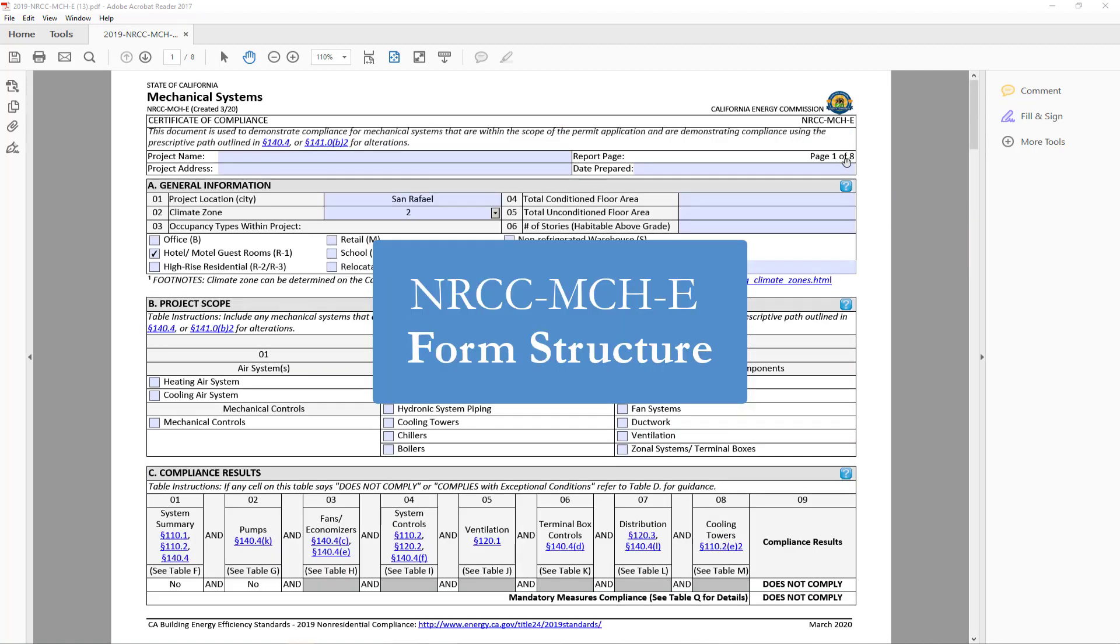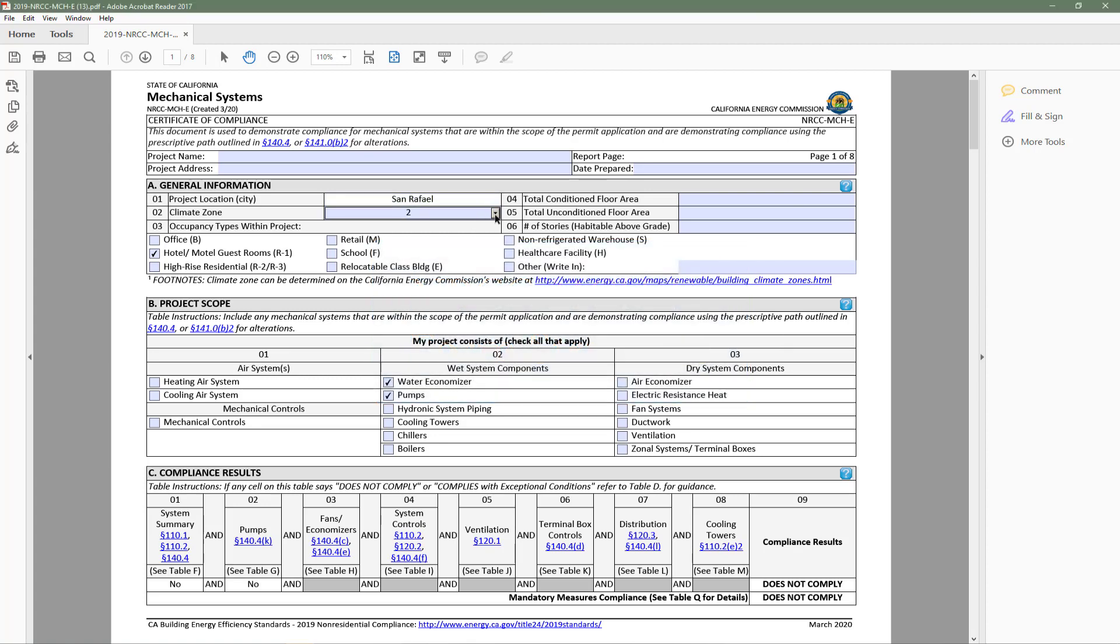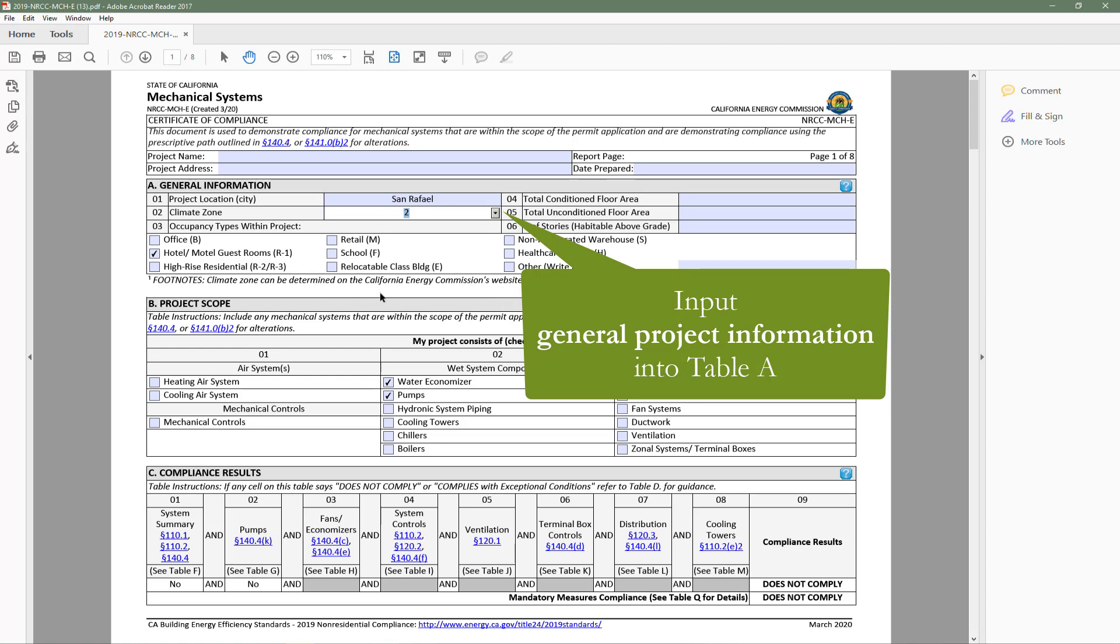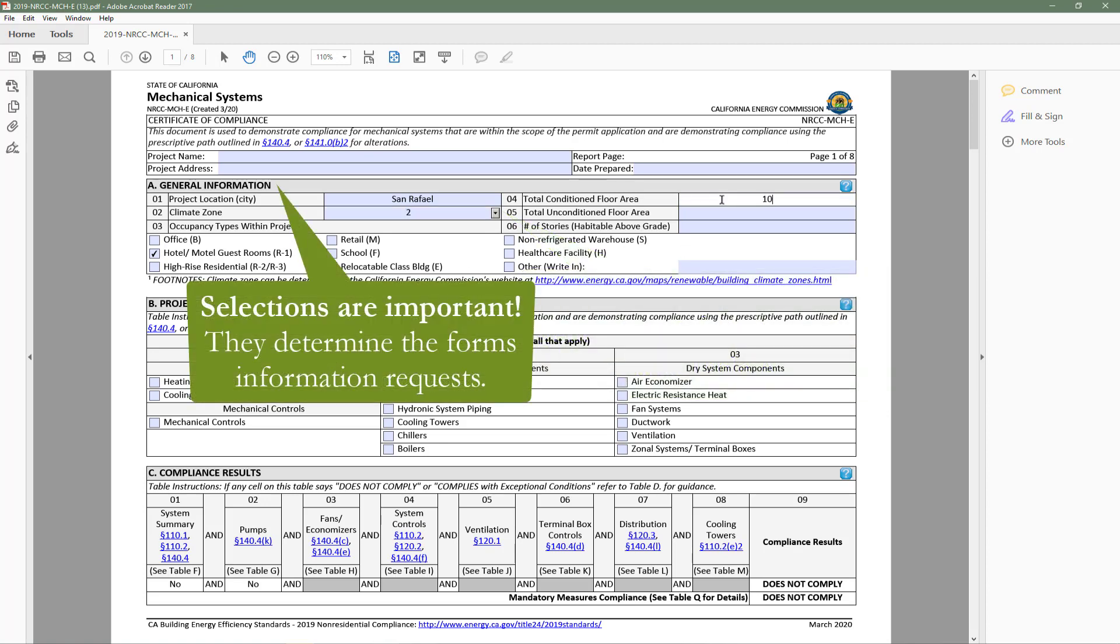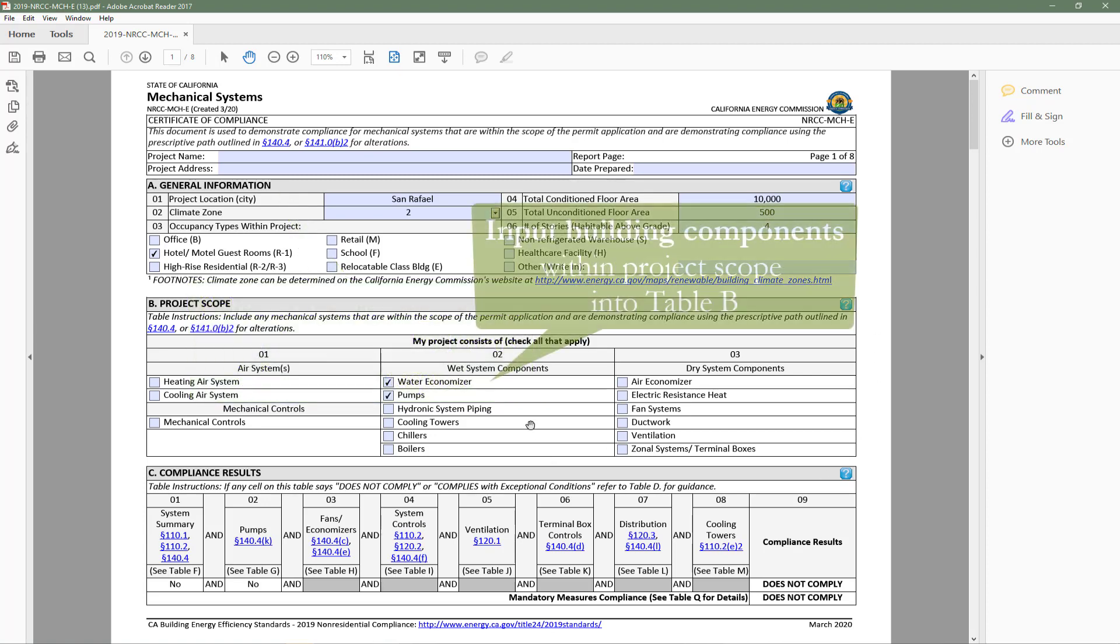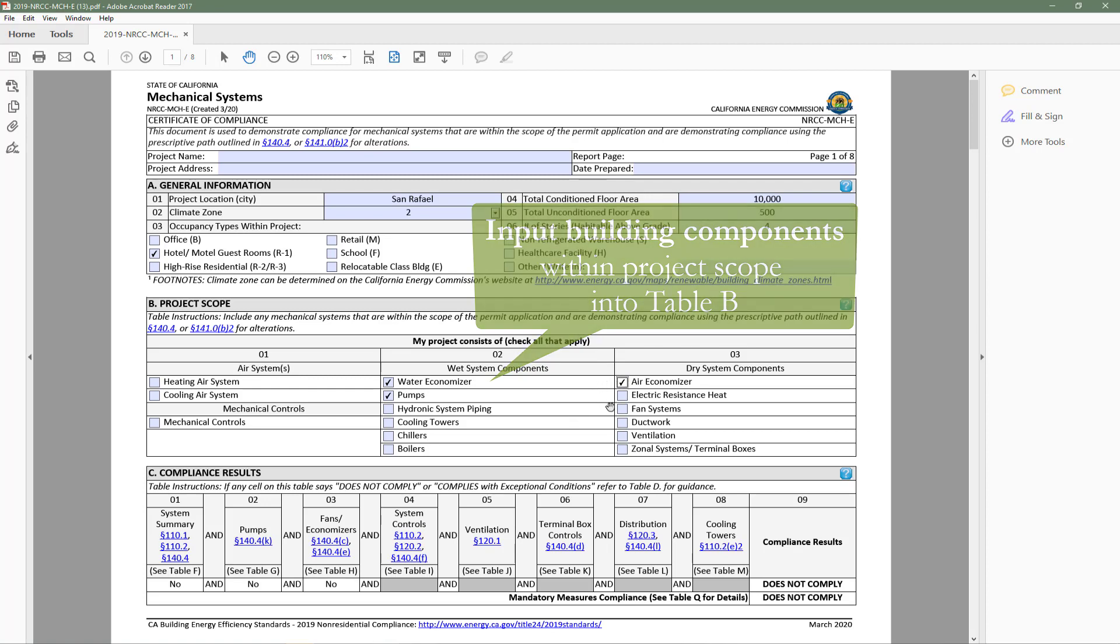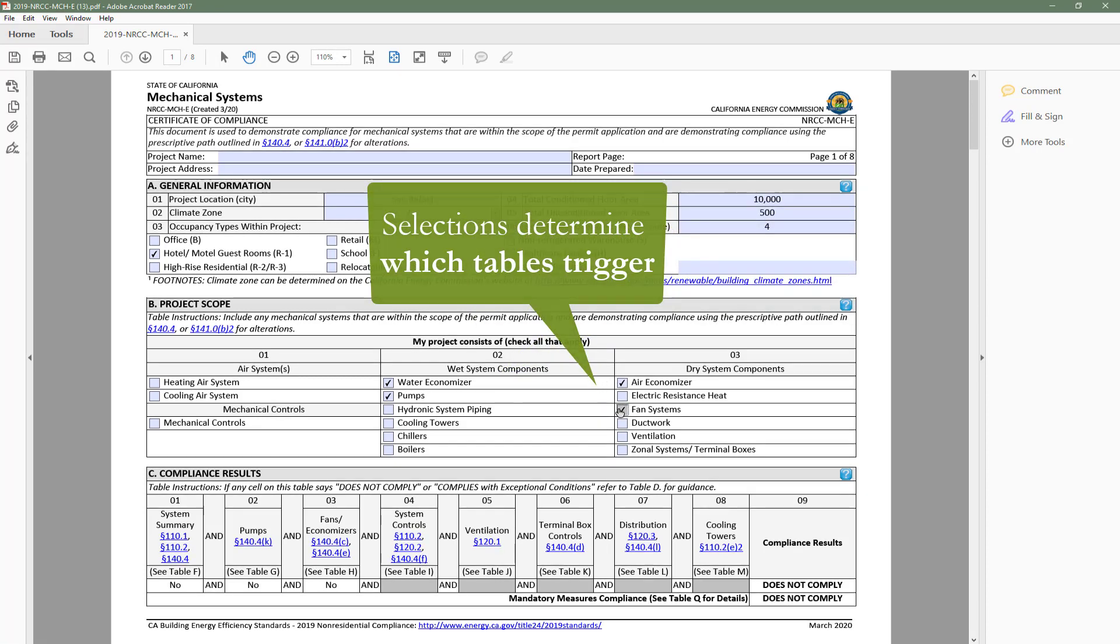Now let's cover the basic structure of the mechanical form. The documentation author will indicate general information in Table A, such as climate zone, occupancy type, and condition floor area. These inputs are important because the form will limit information requests to only the requirements that apply to those climate zones, occupancy types, and condition floor area. The documentation author will then input their project scope in Table B.